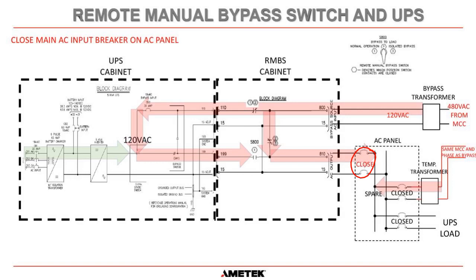So now we're feeding power from the bypass transformer back down out through the UPS loads. But remember, still in parallel with the temporary transformer. Okay, I hope that makes sense. And once again, we take an amp clamp and we want to see current flowing through this breaker. Now, here's a confusing thing. Remember, this transformer and this transformer are now operating in parallel. You may not see the full 20 amps at this point. It depends on the voltages and the length of the cable drops and all that kind of stuff. You could see 10 amps here and you could see 10 amps here. But really what you're checking for is to make sure there is current flowing through that breaker to make sure that it did actually close.